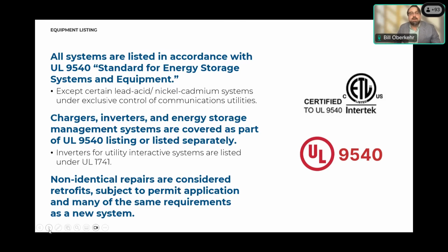It is required by code, not to be confused with the UL 9540 field listing. The UL 9540 field listing is not a suitable replacement for the UL 9540 equipment listing. That is crucial to understand.